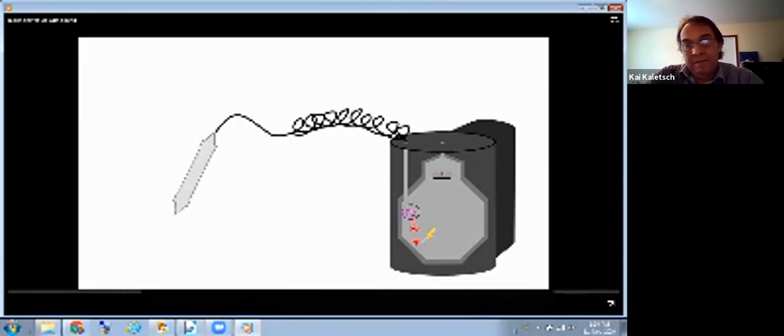The half-life of radon decay products is short enough so that they decay away overnight. But if you leave radon gas in the cell by not properly flushing with clean air before shutting off the sniffer, that has a 4-day half-life. That doesn't disappear overnight. Plus, it will have created radon progeny all night long.